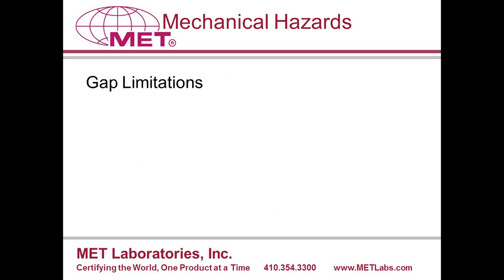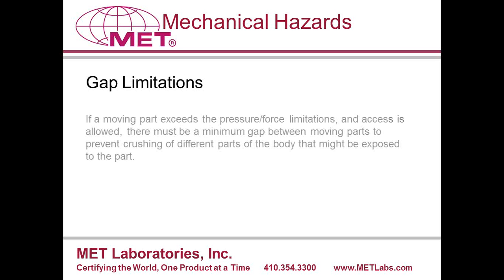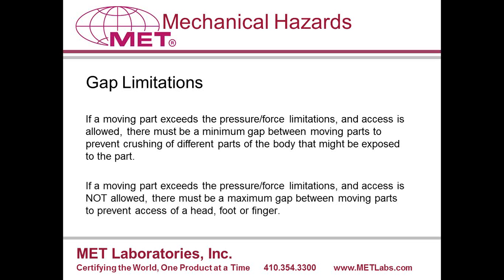Third edition also defines minimum and maximum gaps to protect users from moving parts. If access to moving parts is allowed, there must be a minimum gap between moving parts to prevent crushing. If access is not allowed, there must be a maximum gap to prevent access.